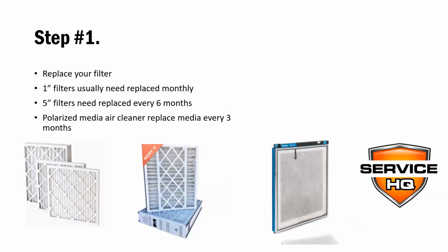So step one, let's get into the maintenance now. Step one is to replace your filter. So 1-inch filters usually need replaced monthly. At most, you could go 60 days, so 2 months maybe. A 5-inch filter, if you have a 5-inch filter, those filters need to be replaced every 6 months. The only reason they can go longer is because there's more surface area.